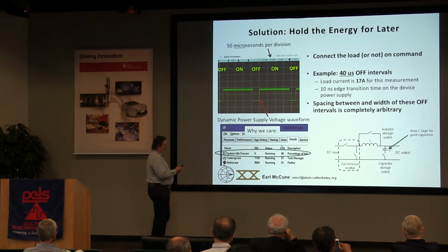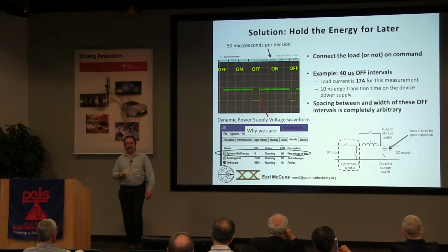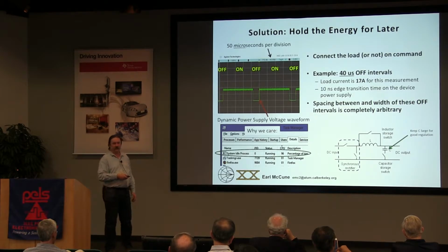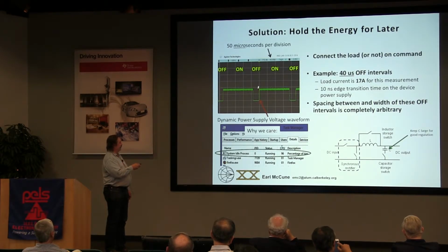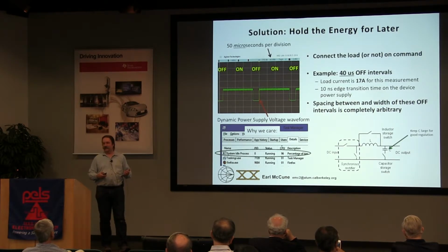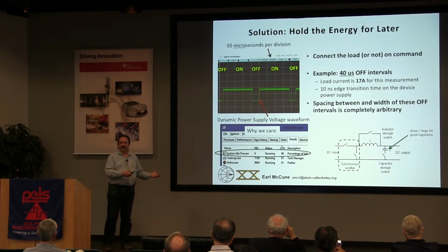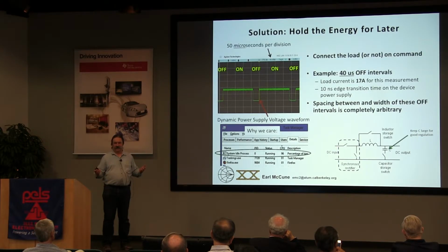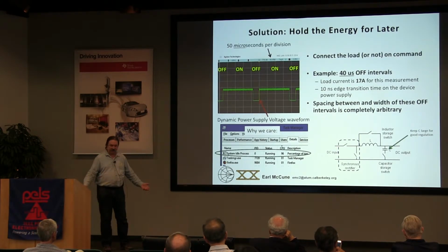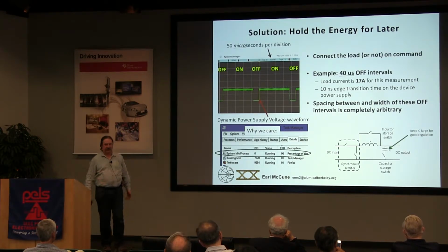How well does this work? This is 10 amps per box, so that's 17 amperes in 10 nanoseconds, with no transient damping needed because there's no control system. It's just the capacitor voltage: we disconnect the capacitor, the load brings it down, reconnect the capacitor, brings it back up. Done.